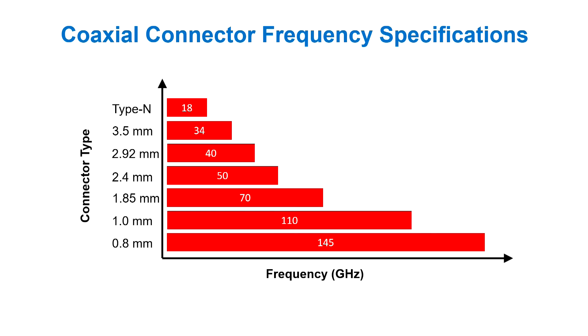So here's a look at the 0.8 millimeter calibration kit we got from Anritsu. There's basically two sets of calibration standards here. There's male and female open, short, and load standards for frequencies 80 gigahertz and less. And then there's a separate cal kit that's basically 3 pairs of offset shorts that are used from 80 gigahertz to 145 gigahertz. And this cal kit also includes 2 verification devices, a matched line and a Beatty line. And we'll compare measurements of these 2 verification devices.